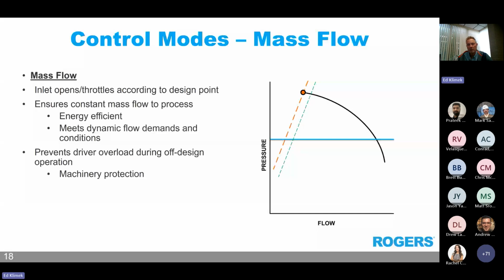So this is really beneficial in different operating conditions where the ambient conditions, such as temperature, pressure, and relative humidity of the compressor location, change the necessary inlet valve throttle percentage to maintain the desired mass flow. Also, mass flow prevents driver overload in off-design conditions.